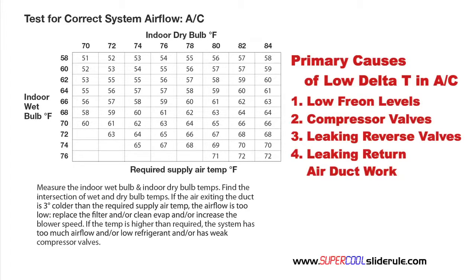And four, leaking return air ductwork. Carefully inspect the return air ductwork for leaks. Also use a type K temperature probe to verify that return air temperature is the same when it reaches the unit as it is at the return air grill.